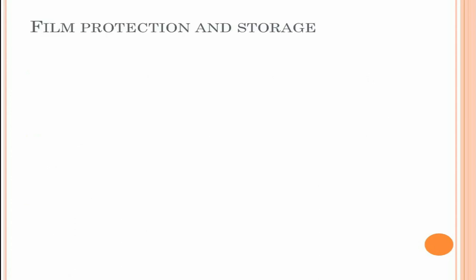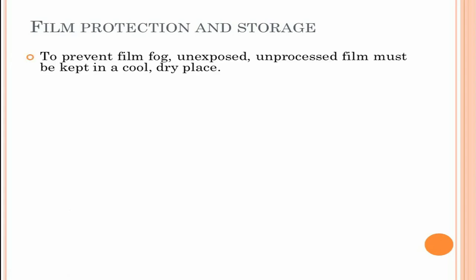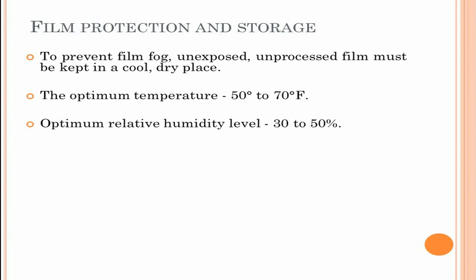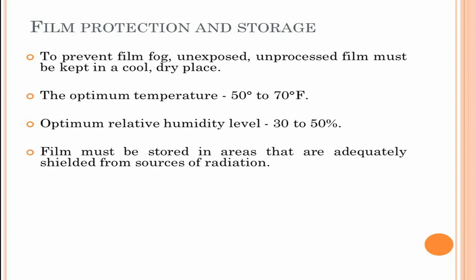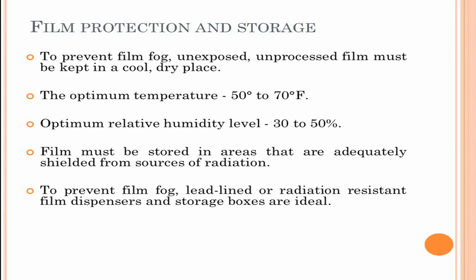Next is film protection and storage. To prevent film fog, unexposed unprocessed film must be kept in a cool, dry place. Film is adversely affected by heat, humidity and radiation. Optimum temperature for film storage is 50 to 70°F and optimum relative humidity level is 30 to 50%. Films must be stored in areas adequately shielded from radiation sources and should not be stored where patients are exposed to radiation. Lead-lined or radiation-resistant film dispensers and storage boxes are ideal. All dental x-ray film has a limited shelf life. Each box is clearly labeled with an expiration date. The first in, first out rule should be applied to film use. The oldest film in stock should always be used before any new film.